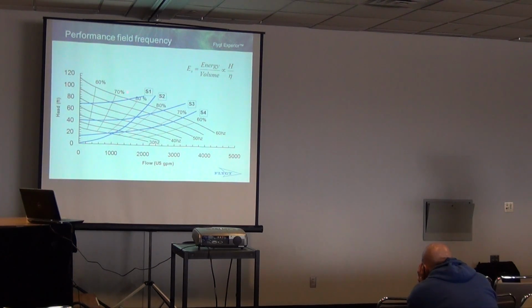If we're going to start a pump, the best efficiency point on this pump right here is around that 80% range. If you look at these different system curves that lay in there, and we were to apply a simple VFD to this curve, number one, we're not in a very good spot of efficiency on that pump selection anyway, are we? If we start to slow that pump down, we're getting further and further away from that BEP, or best efficiency point, on that curve like you see there.